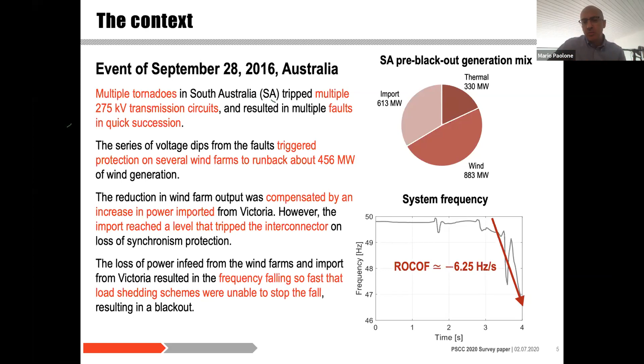However, this increase of the imported power was overloading the interconnection, and the loss of the import from Victoria resulted in a frequency that was falling so fast that load shedding was simply unable to recover the power balance, and then the frequency collapsed. What was learned from this event was a pretty high rate of change of frequency, what we call ROCOF. It is reported here for a specific time window of the event, and the measurement was an average of 6.25 hertz per second, which is a pretty extreme value that is challenging phasor approximations, as we'll see in a moment.